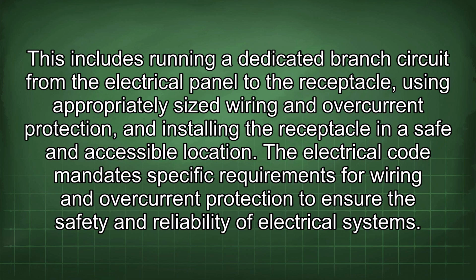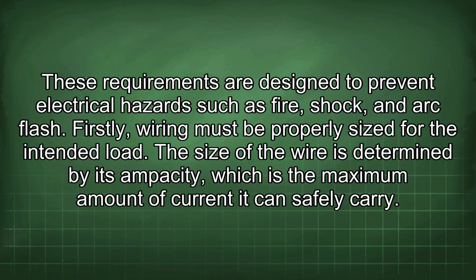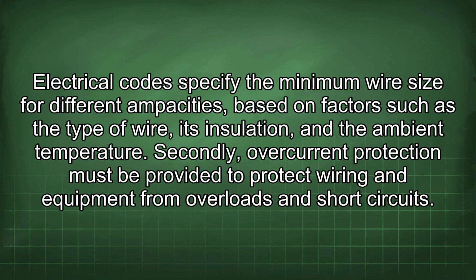The electrical code mandates specific requirements for wiring and overcurrent protection to ensure the safety and reliability of electrical systems. These requirements are designed to prevent electrical hazards such as fire, shock, and arc flash. Firstly, wiring must be properly sized for the intended load. The size of the wire is determined by its ampacity, which is the maximum amount of current it can safely carry. Electrical codes specify the minimum wire size for different ampacities, based on factors such as the type of wire, its insulation, and the ambient temperature.